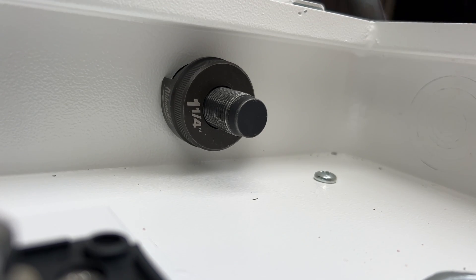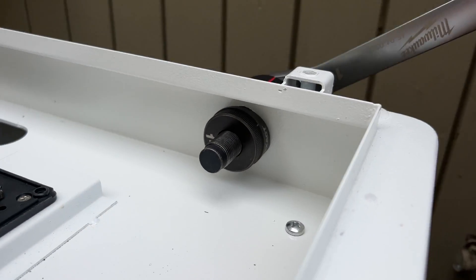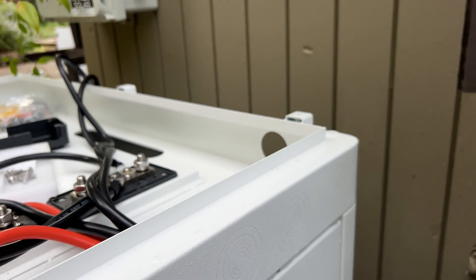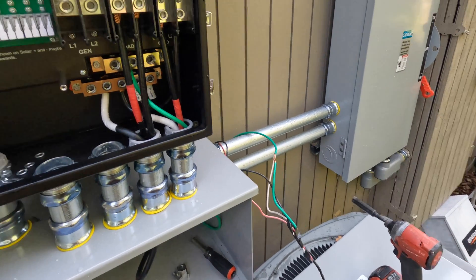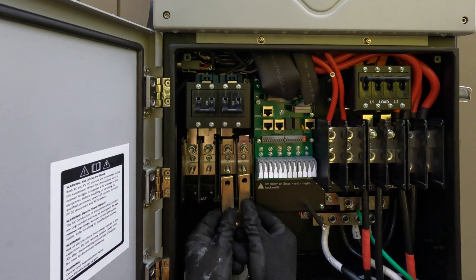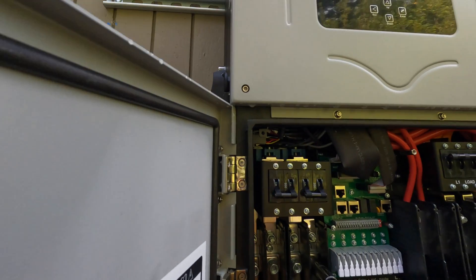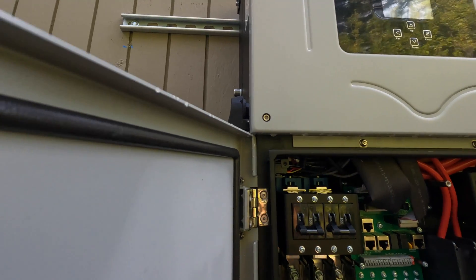The battery cabinet has 1.25-inch knockouts on the right side, but in my case that didn't work, so I'm making a new knockout on the back side of the cabinet. If you are planning to install Sol-Ark, I highly recommend getting bus bars for the batteries — that way you only have to run 2 wires to the battery instead of 4 wires if you're not using those bus bars.